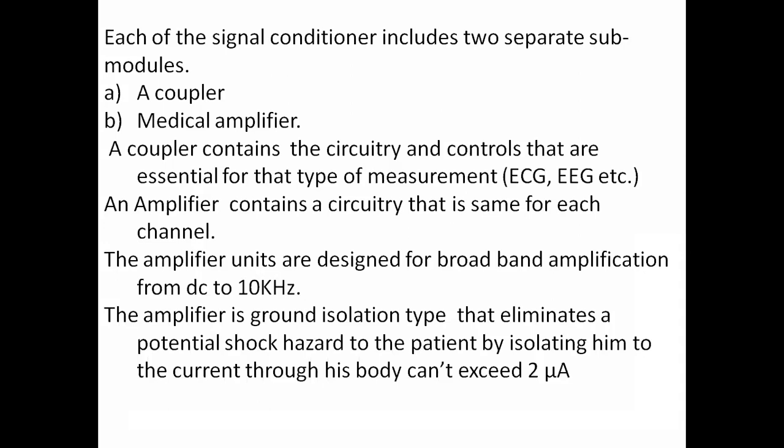If for any reason any part of that power supply is connected to the patient through the scanning section, that leads to a shock for the patient. So that situation should be avoided. Isolation of the shock for the patient is also provided by this amplifier.